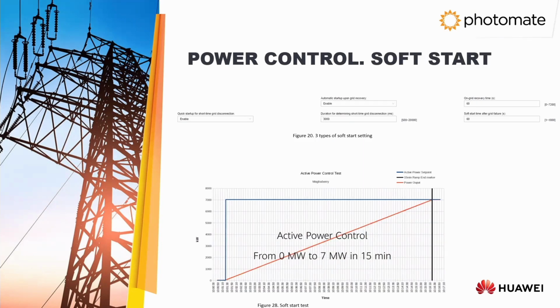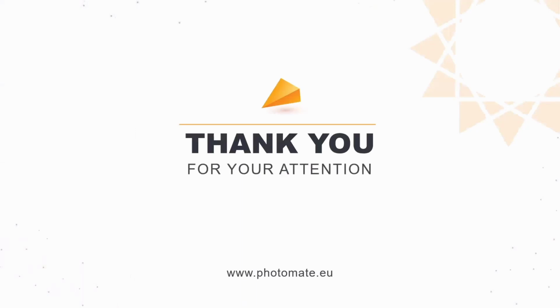And I can see that I am over the time. So the last final control feature is about startups of the inverter and the change of the power. The inverter can be controlled in how it starts, because it will not be good for the grid if the inverter starts very rapidly. So there is the possibility to set the parameters: how the inverter should start, how it should start after some fault, and how it must change the power during normal operation. So all three functions are available. Okay, that's it. Thank you.